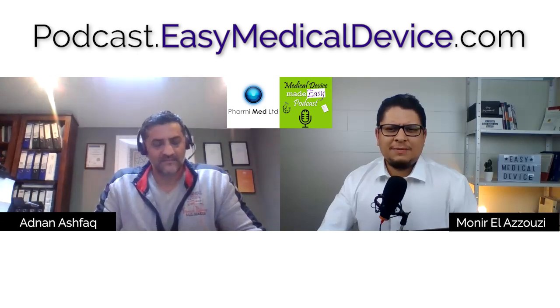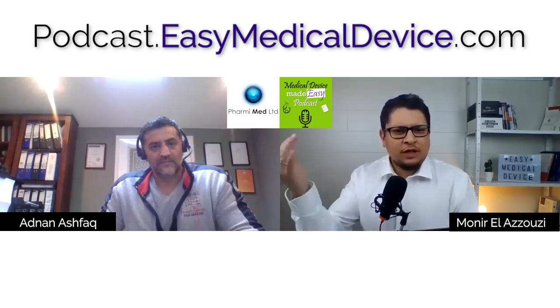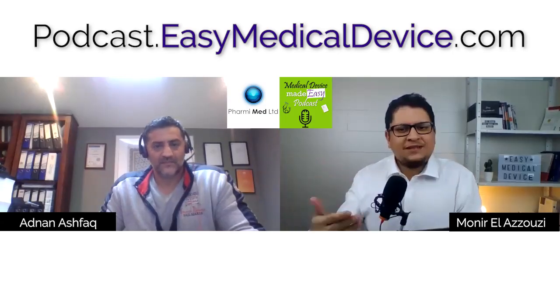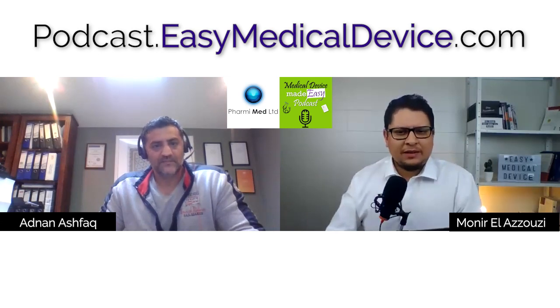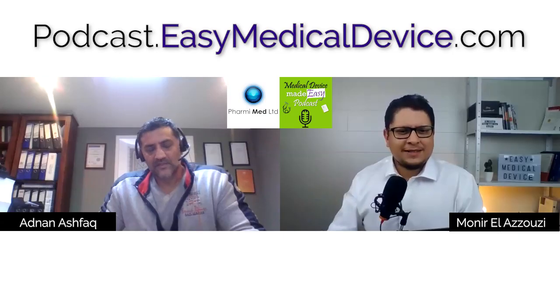Okay, so mainly you have to put in place a kind of monitoring process. So when you say you have to check, it's not something you define later, you define it now. You check every 2 months, 3 months, or 6 months. You have to define that in your validation plan and revisit it as mentioned. Yeah, I think this is what the auditors will be checking, whether the report mentions the frequency of revalidation, rechecking, or monitoring.